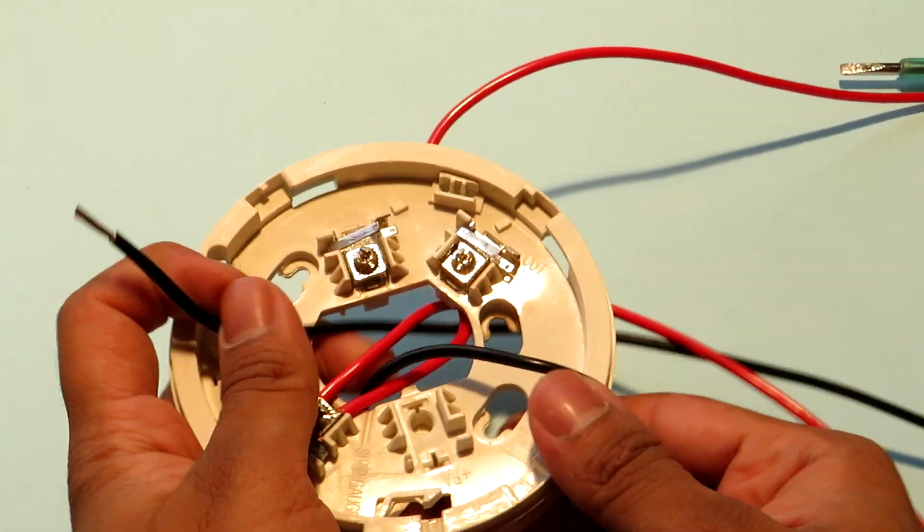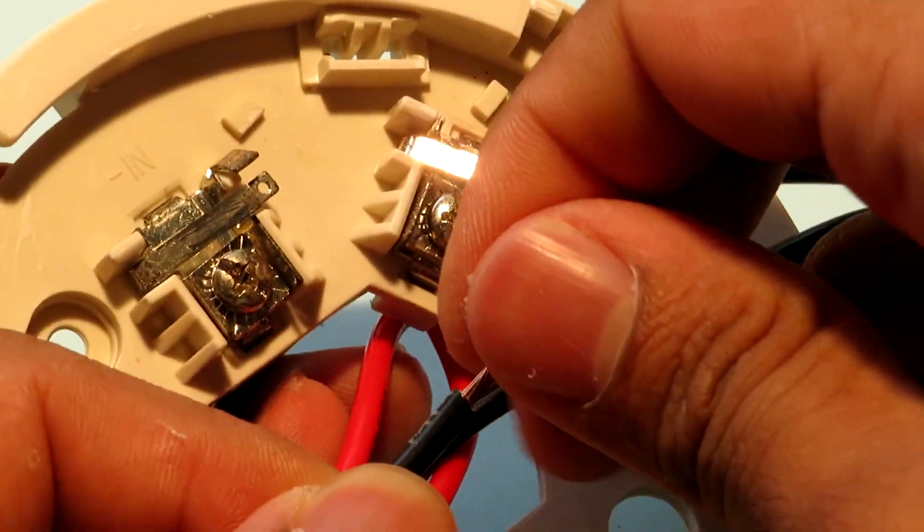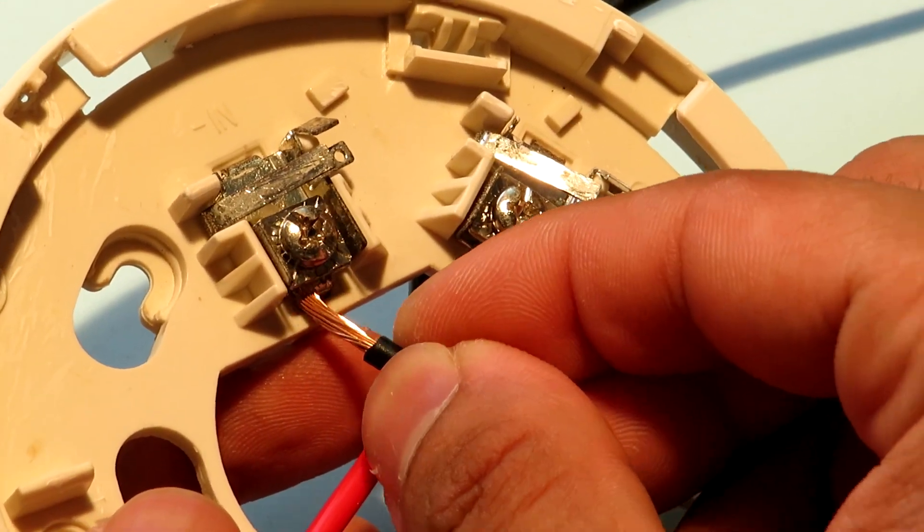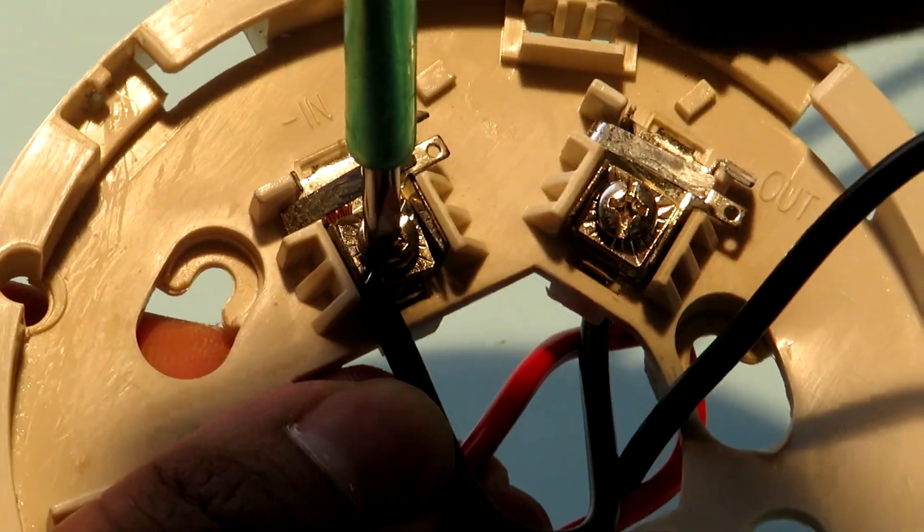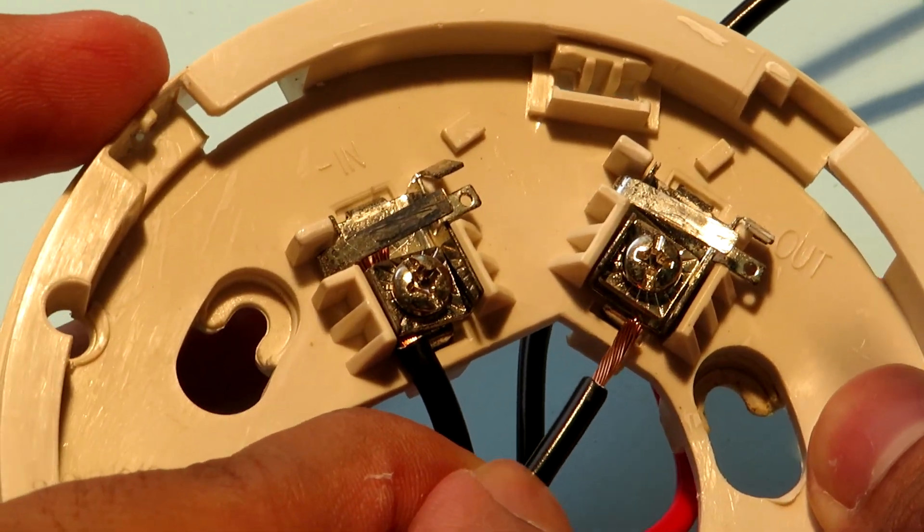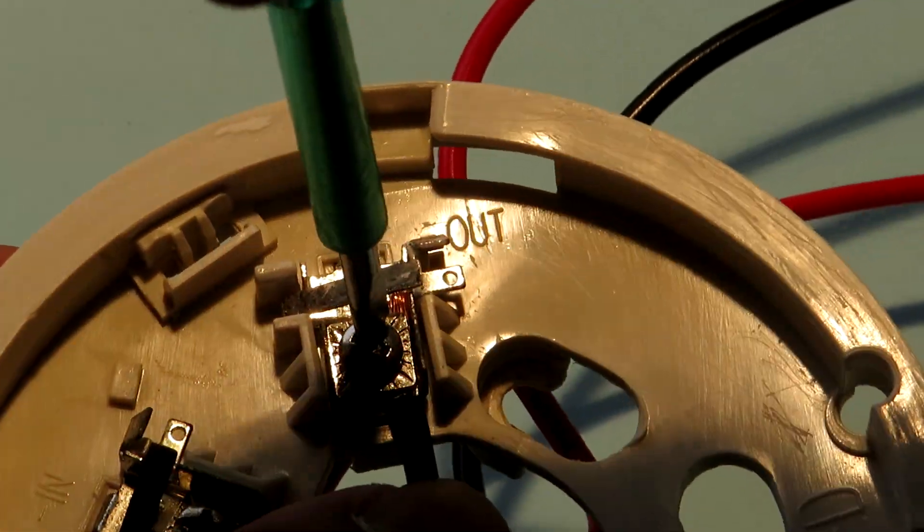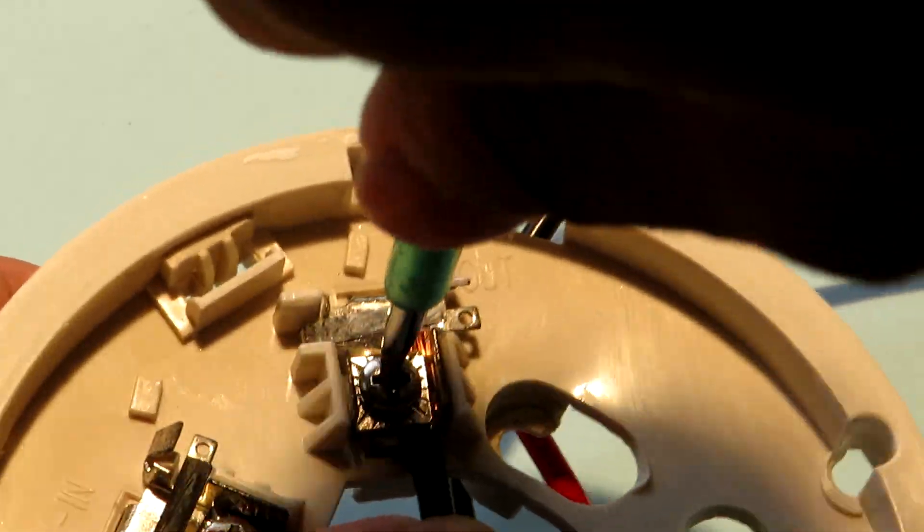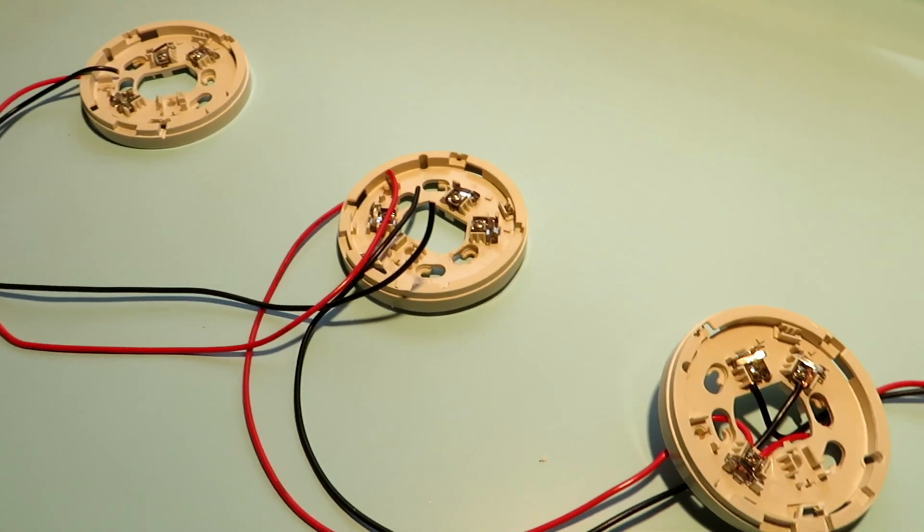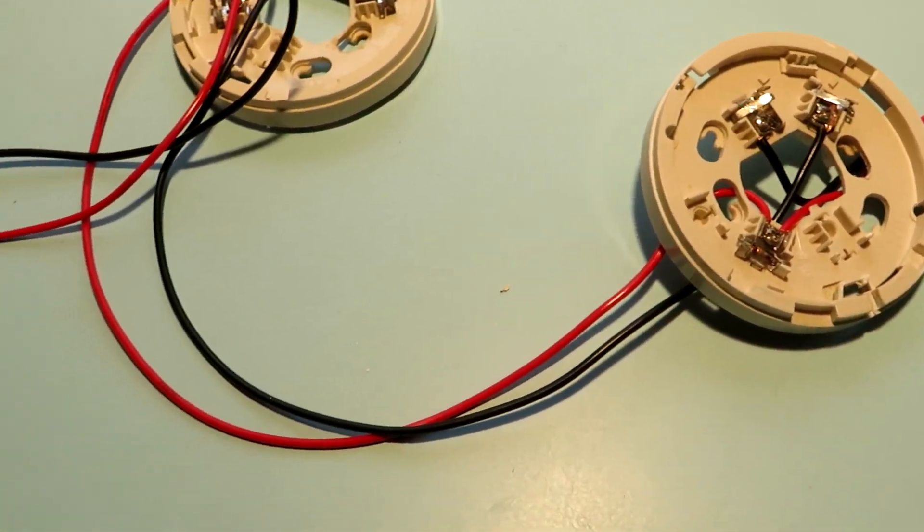Coming to the negative wires, the incoming wire from the fire alarm control panel will go to the terminal labeled negative in. The negative wire going to the next detector in the line will go to the terminal labeled negative out. Practically it doesn't matter even if you interchange negative in and negative out because the sole purpose of it is just to check the continuity and interchanging in and out will not matter there. So we have successfully connected our first detector in the line.